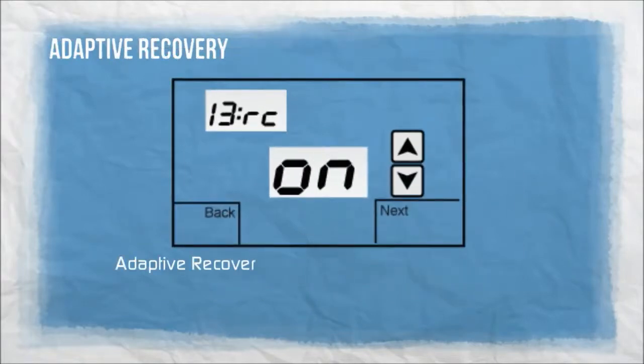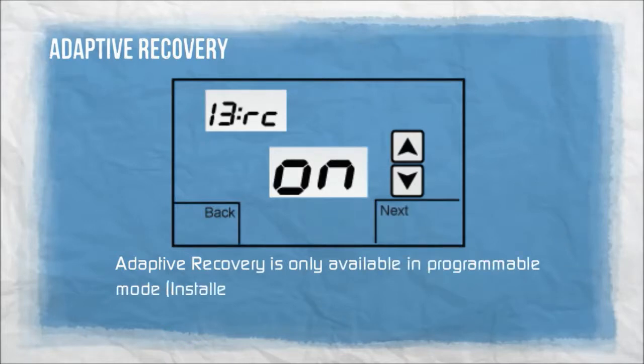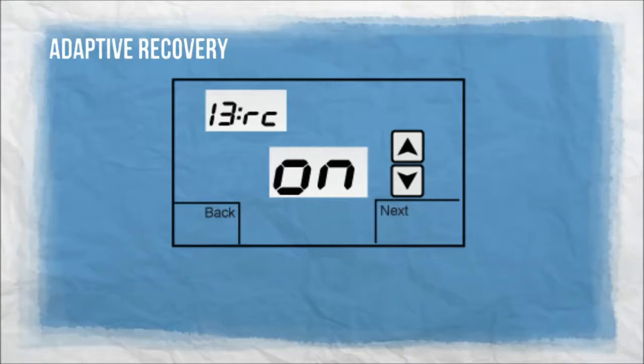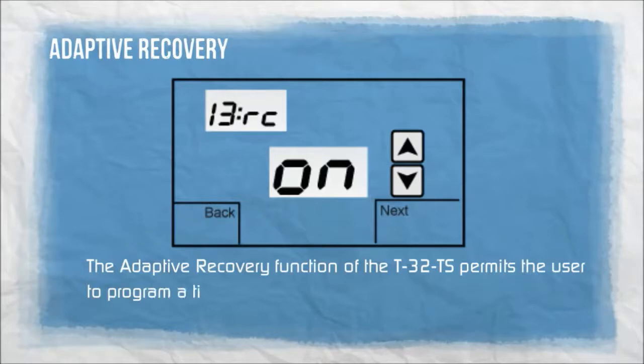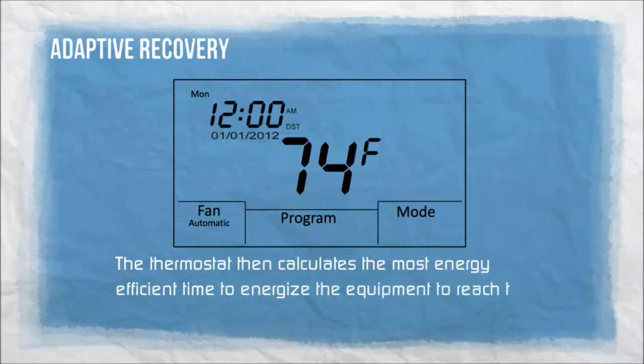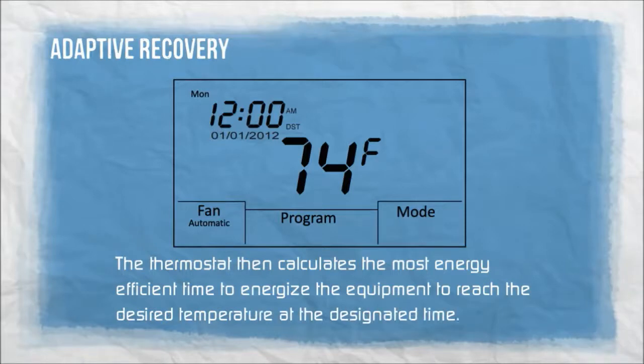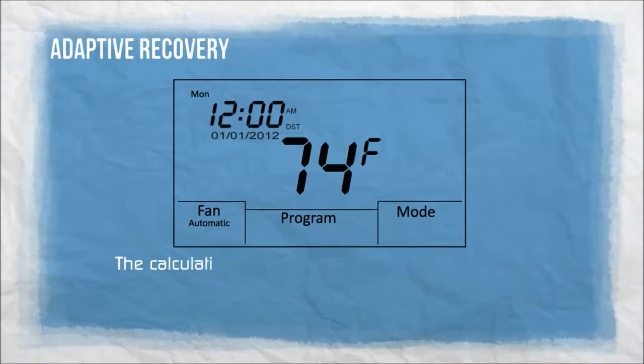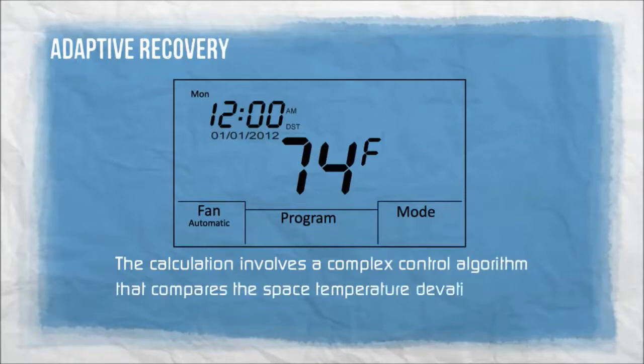Adaptive recovery is only available in programmable mode — installer option menu 13RC equals ON. The adaptive recovery function of the T32TS permits the user to program a time the desired set temperature is required. The thermostat then calculates the most energy efficient time to energize the equipment to reach the desired temperature at the designated time. The calculation involves a complex control algorithm that compares the space temperature deviation from the set point and rate of recovery history.